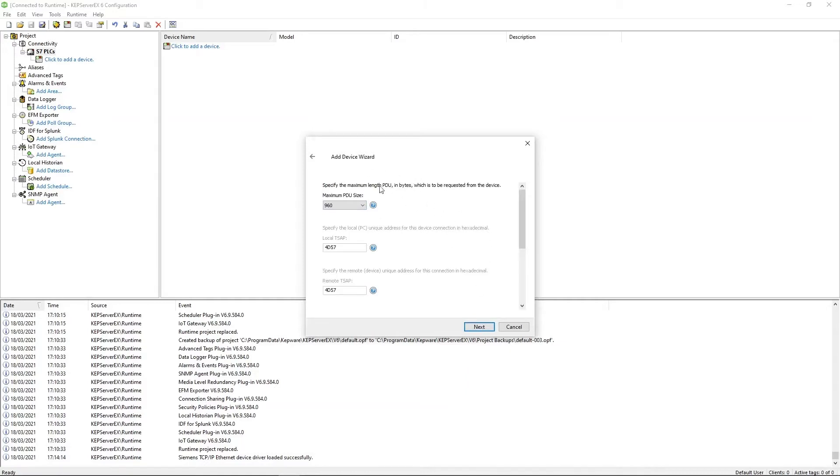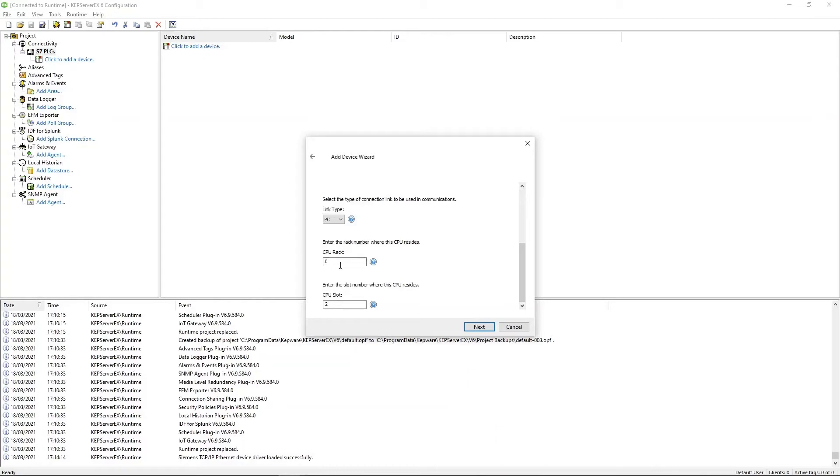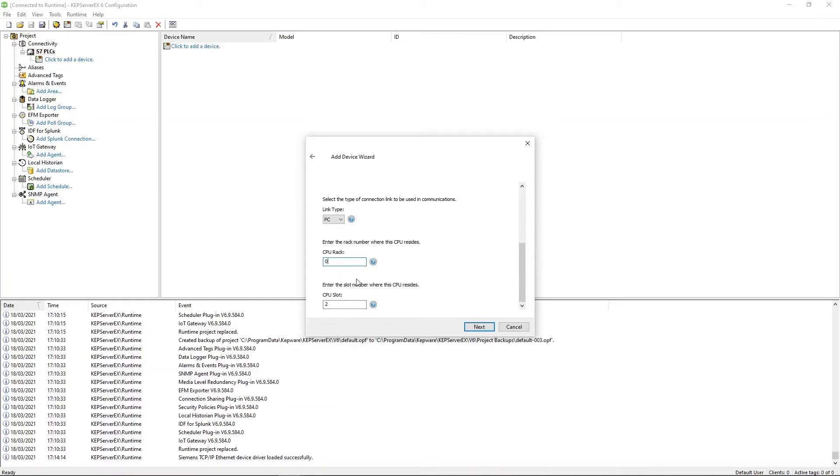These are specific low level kind of packet size options. So you have your maximum PDU size, which will be negotiated between Kepware and the device itself. But if you want to set it lower, you can do that if you need to for your network. But down here are two very important numbers. This lets you specify the rack and slot of the CPU that you're connecting to. And for the S7300, it's always going to be 0 and 2. And for the S71500 and S71200, it's going to be 0 and 0 or 0 and 1, they both work. But for other devices, these could be entirely different. It entirely depends on the specific configuration of the cabinet. So you have to make sure these are right or the communication won't work.